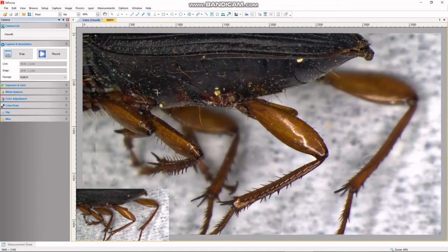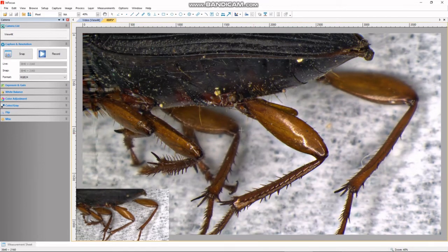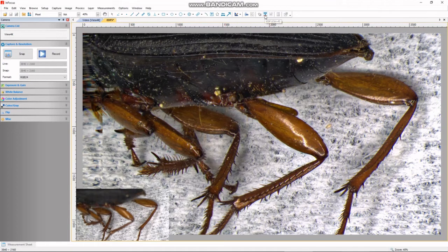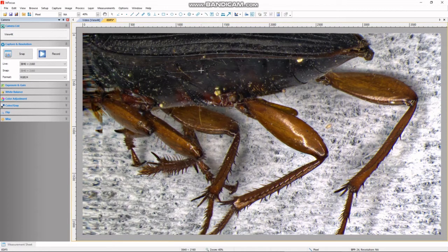Going halfway through, you can see this part is in focus — the top legs of my specimen are in focus — and I'm now getting down to the bottom part. You want to go all the way through from top to bottom. Don't go too far past either end, but you definitely want to encompass all of the focal plane. When done and happy with the results, we click the same EDF icon to end the extended depth of focus capture.